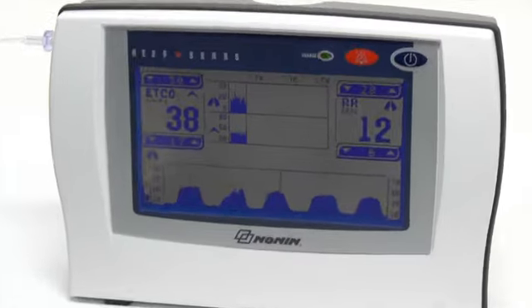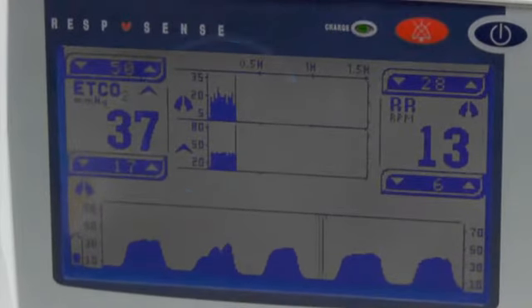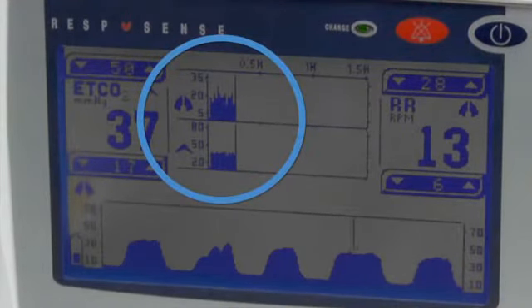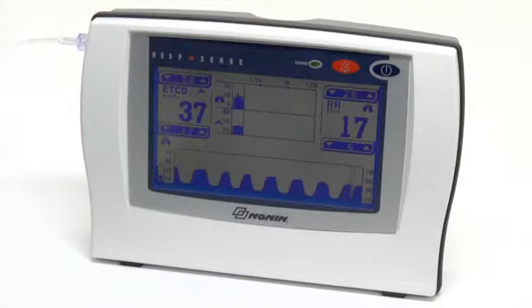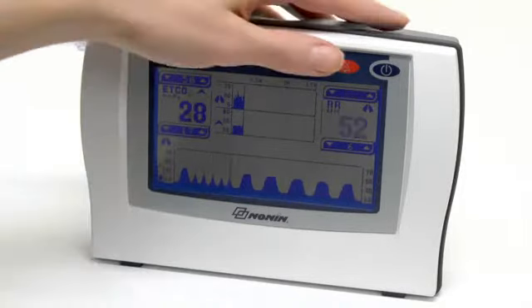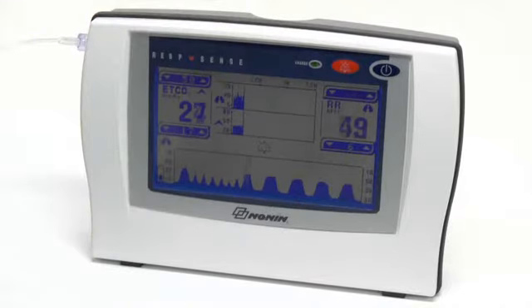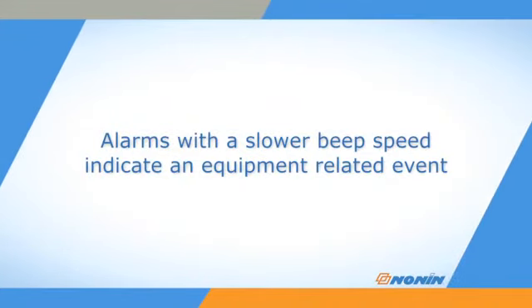The trend graphs indicate the end tidal CO2 and respiration rate trends for the last 1.5 hours, with markers at half-hour increments. The monitor will alarm if the end tidal CO2 or respiration rate goes outside of your set limits, or if no breath has been detected for 25 seconds. You will hear a rapid beep sequence and a flashing of the limit exceeded on the display. Other alarms with a slower beep speed may occur, indicating an equipment-related event you need to resolve.